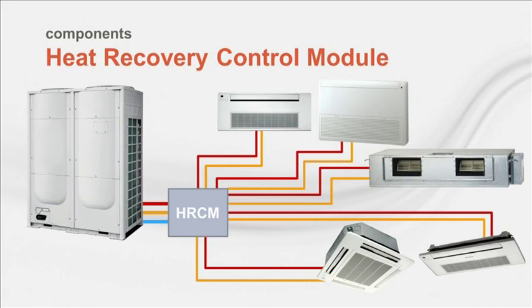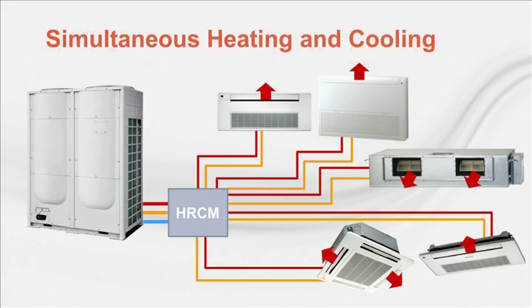As conditions change, some zones will require cooling. The heat recovery control module allows some units to cool and others to remain heating at the same time. 2 zones now require cooling, while the remaining zones continue to need heat. The heat recovery control module is able to route low-temperature liquid refrigerant to the indoor units that require cooling while sending high-temperature gas to the indoor units that need heat.